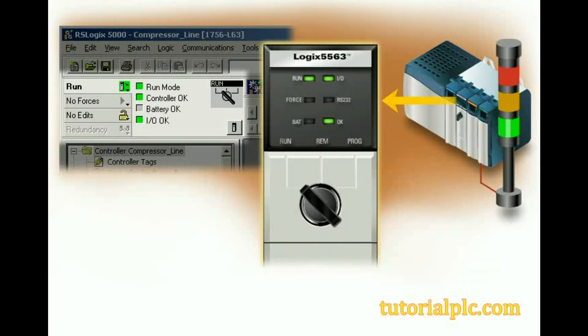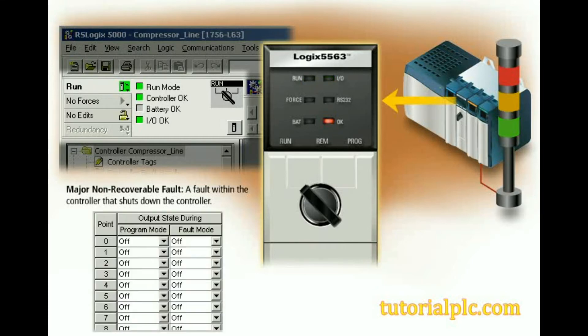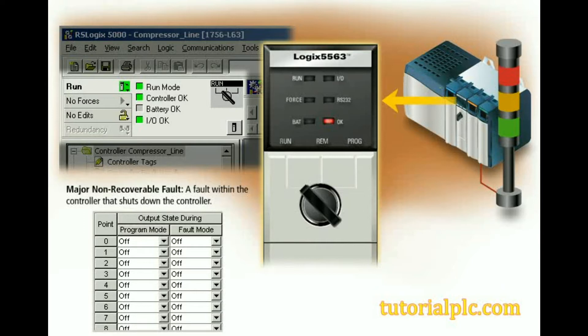A major non-recoverable fault is a fault within the controller that shuts down the controller. The following changes take place when a major non-recoverable fault occurs: the controller OK LED turns solid red, outputs change to the fault state selected in the I.O. configuration. Fault states can be on, off, or hold, and the online toolbar displays the word faulted.